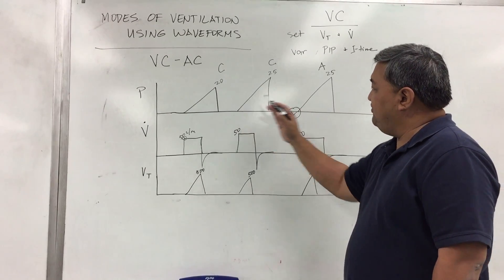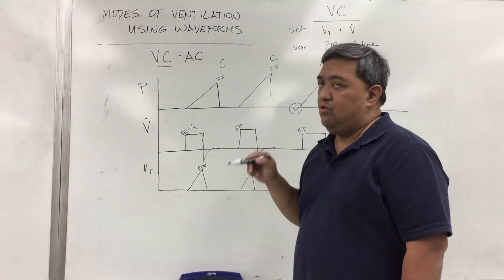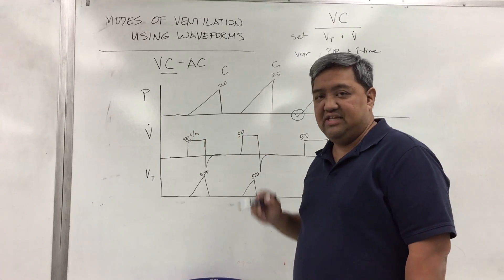Any combination of these two is your assist control mode. It is volume control because you have a set volume and a set flow.